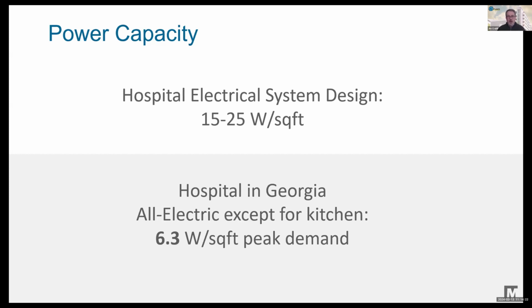Looking at typical hospital electrical system design, we see some variation of the power infrastructure, but it's somewhere around 15 to 25, maybe even 30 watts per square foot, depending on the jurisdiction and some of the rules. But we've got a hospital here in Georgia that is all electric except for the kitchen, and it's only running actual measured load about 6.3 watts per square foot. So that would tell me that all electric can fit within the infrastructure that we typically design in a hospital.